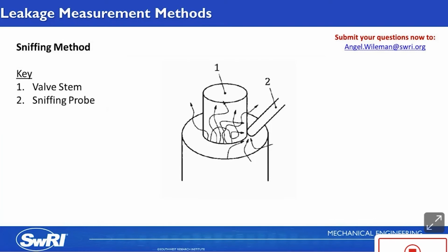The last method is the sniffing method, and this is used by API standards, ISO standards, and EPA Method 21 to measure leakage. The instrument detector probe sniffs the local emission around the stem and body seals. While measuring, it's important to keep the probe as close as possible to the leak source. A helium mass spectrometer or another type of instrument may be used for testing with helium. It's important to consider weather effects if you're using this method because high winds can affect your reading. You want a calm environment. Also, it's important to consider temperature stability because the vapor pressure will increase at increasing temperatures, and this can affect your concentration measurement.